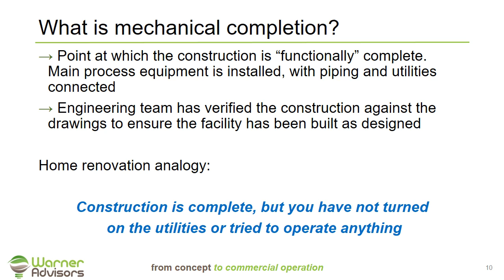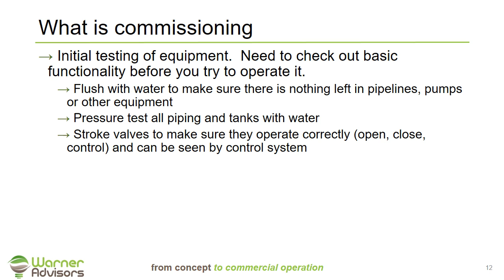You'll flush equipment with water to make sure there's nothing left in the pipelines, pumps, or other equipment. You'll pressure test all of the piping and tanks with water to make sure they'll hold their proper pressure rating. You'll stroke the valves to make sure they operate correctly, opening, closing, and controlling the way the control system shows them to be operating. You'll test pumps to make sure they work and can be controlled from the control system. And you'll run systems on water to set initial calibration and flow of the systems.